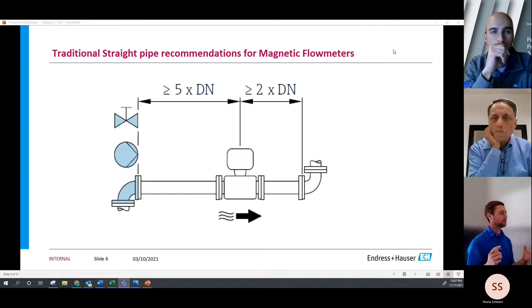So moving into what we're going to talk about today: the first product that E&H patented and released, I think maybe two and a half years ago now, is built for reduced straight run requirements. This device is a magnetic flow meter. What it did is take the convention of needing straight run requirements to create a laminar, homogeneous flow profile—for a nice, consistent, accurate reading—and built a hardware solution that reduces those straight run requirements. Convention is 5 pipe diameters upstream and 2 pipe diameters downstream, again to get that laminar homogeneous flow profile, because traditional mag meters have measuring electrodes on either side—only one electrode on each side—inducing a voltage proportional to the flow velocity.